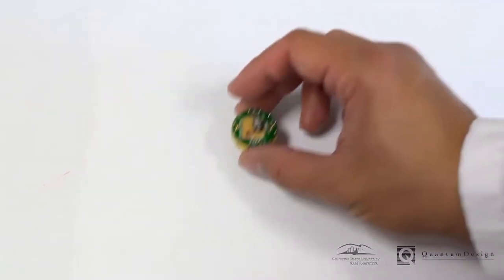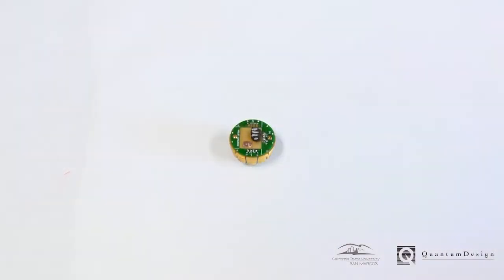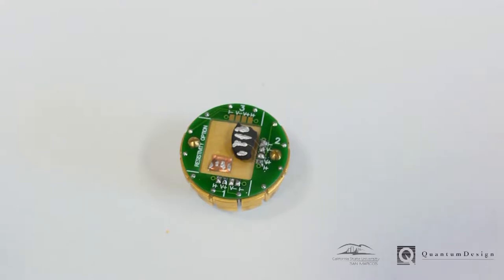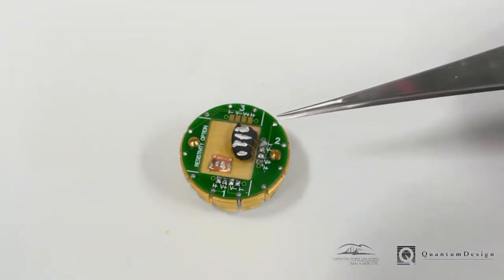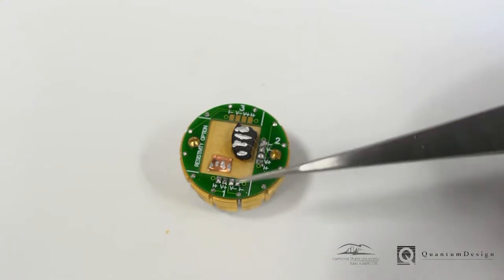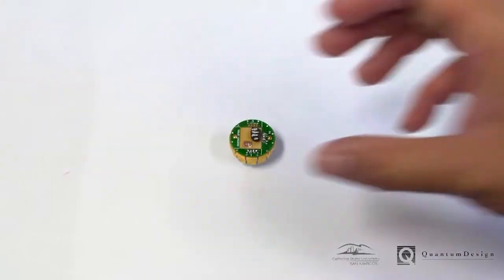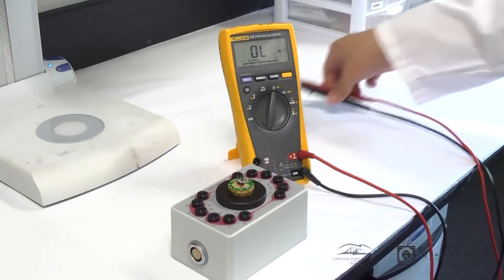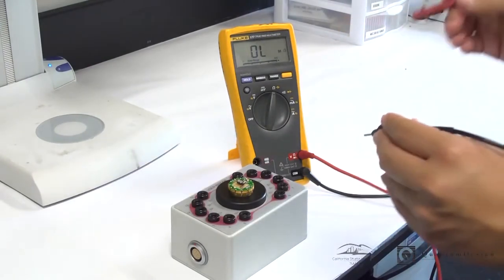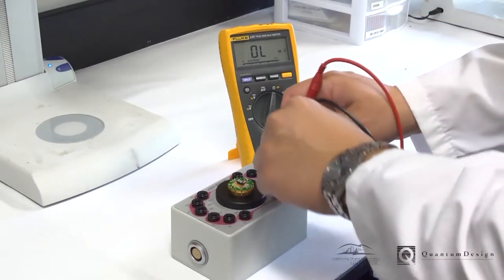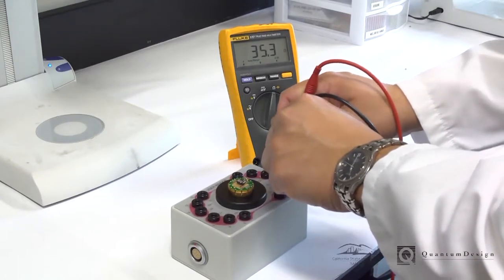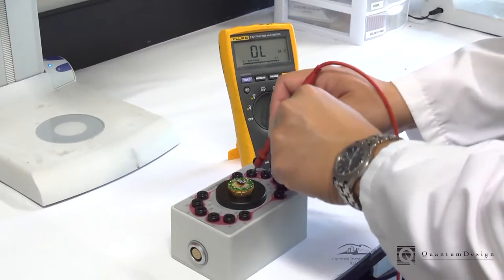Two channels are available for simultaneous measurement, and samples can be wired in either two-wire or four-wire measurement configurations. You may solder directly to the puck pads. Here we have a sample of YBCO superconductor and a sample of copper foil connected by platinum wires and silver paint. It's a good idea to check your contacts before you load the puck into the VersaLab. You can use the puck box and a standard multimeter to check to see whether you have made good ohmic contacts.